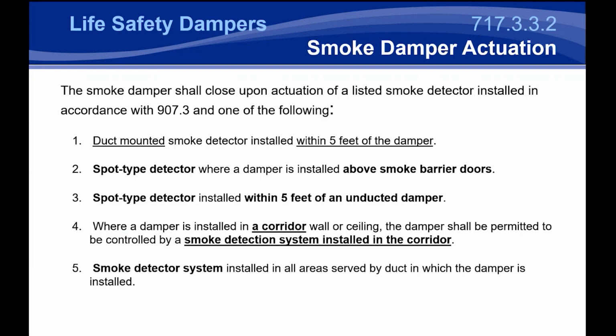As far as smoke damper actuation goes, there's a few different allowances in Chapter 9. And really, what I recommend is what's cheapest for the building owner. Now, if you're dealing with a tenant improvement project that doesn't have a unified smoke control system or a building-wide smoke control system, or you're not in a corridor where you can utilize other types of smoke detectors in the building, by all means, you can certainly have the smoke detector supplied with the damper. The one caveat to that is there's really no damper manufacturer that offers an annunciated smoke detector because we really aren't going to know, and typically the mechanical contractors aren't going to know, what system is going to be put in place. So most of the time I recommend the smoke detectors be supplied by the controls contractor if they need to be annunciated or it's part of that smoke control system.